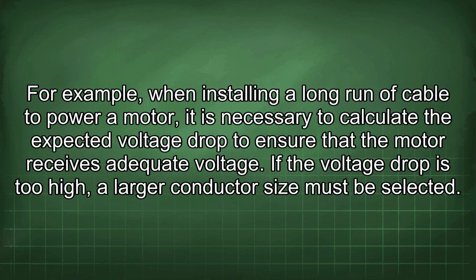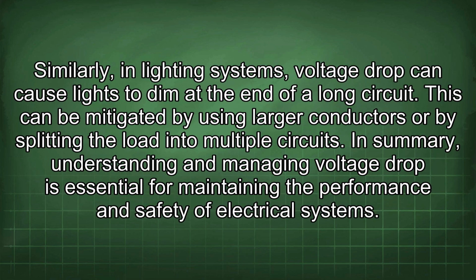For example, when installing a long run of cable to power a motor, it is necessary to calculate the expected voltage drop to ensure that the motor receives adequate voltage. If the voltage drop is too high, a larger conductor size must be selected. Similarly, in lighting systems, voltage drop can cause lights to dim at the end of a long circuit. This can be mitigated by using larger conductors or by splitting the load into multiple circuits.